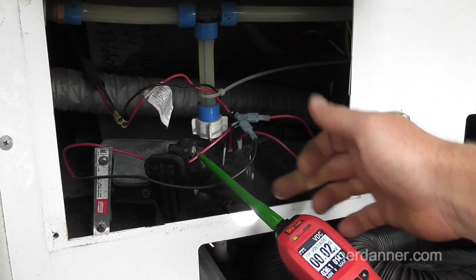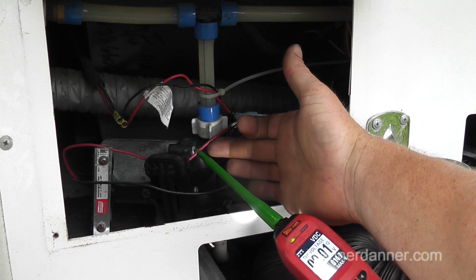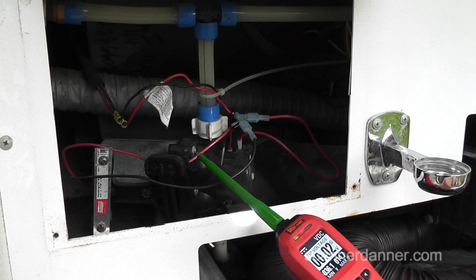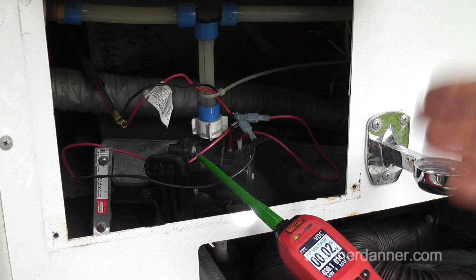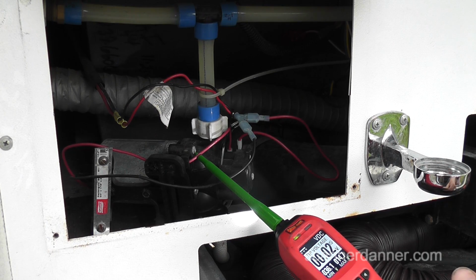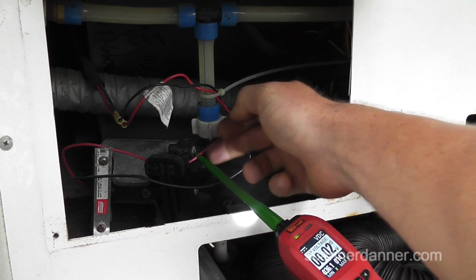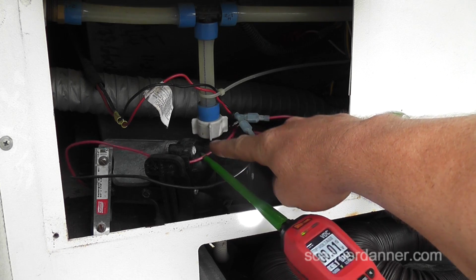So when that happens, it would be normal to have a voltage drop on the feed wire because that's what the switch does. But while the pressure was very low and it was surging, it should not have been doing that. And what I now know is that surging we were seeing was coming from an interruption in the power supply where it shouldn't be doing that.